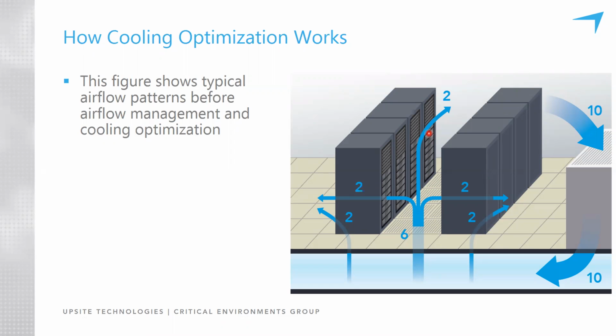You could turn off all the cooling units and there would still be 4 units of air moving through all the IT equipment. You could turn on an extra dozen cooling units and there still will be 4 units of air moving through the IT equipment. They have their own fans and those flow rates are independent. There are a few caveats to that when you get into the details, but that concept is generally true.